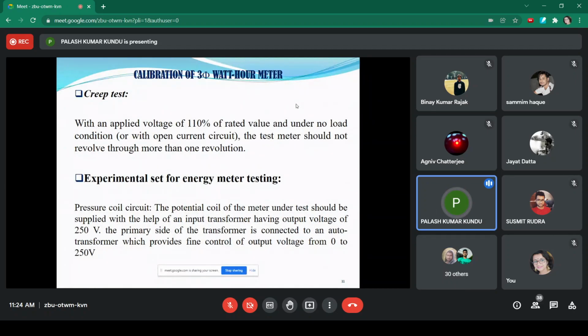So what will happen? Due to the splitting of the two fluxes, even though there is no series flux, a phase difference angle with a very small value will result, and that will cause a slow rotation of the induction disc, even when the series magnet is not excited. This slow rotation is called creep. As per the limit, creep should be around half a rotation per 24 hours or so, very small. That is allowed, but creep cannot be avoided.